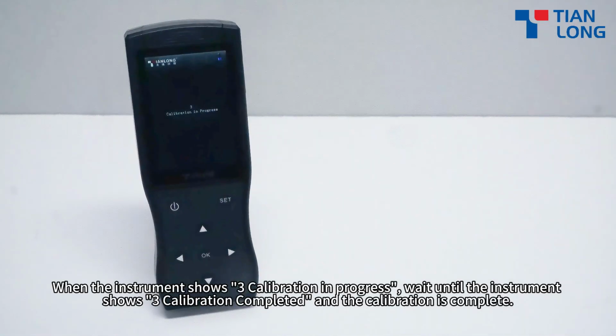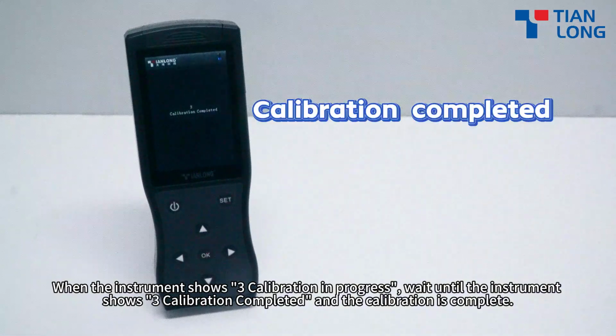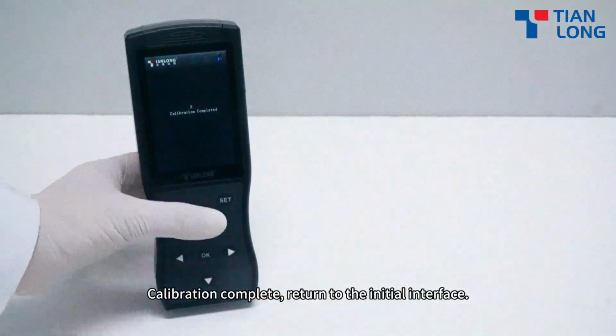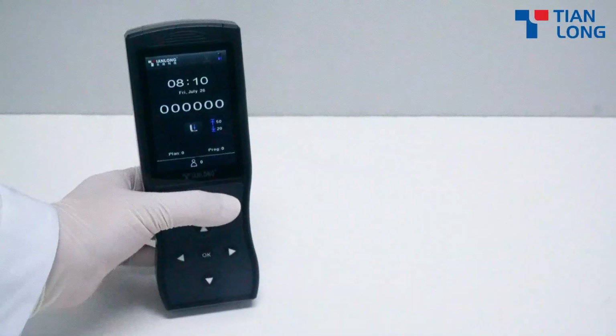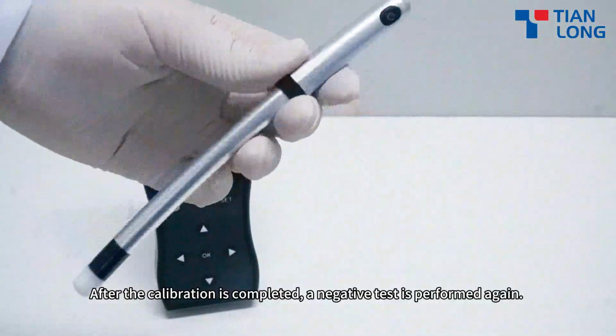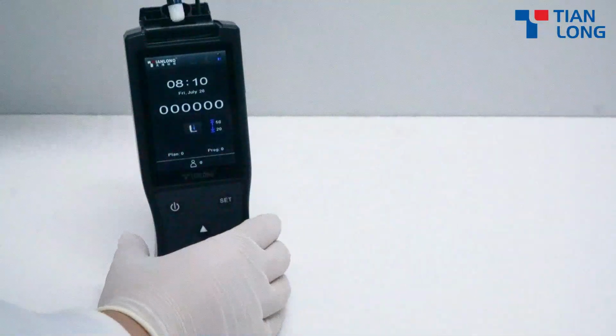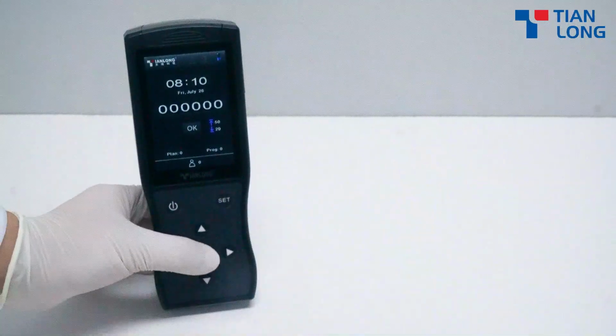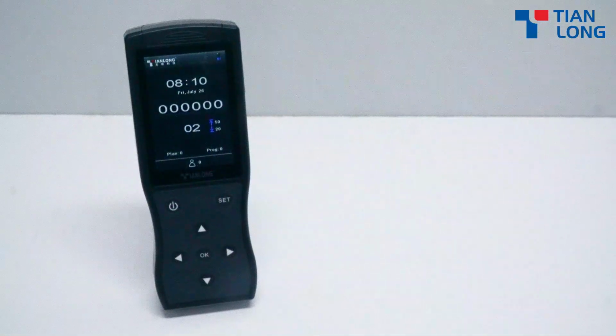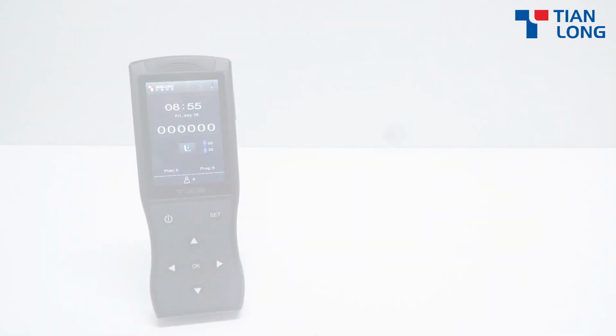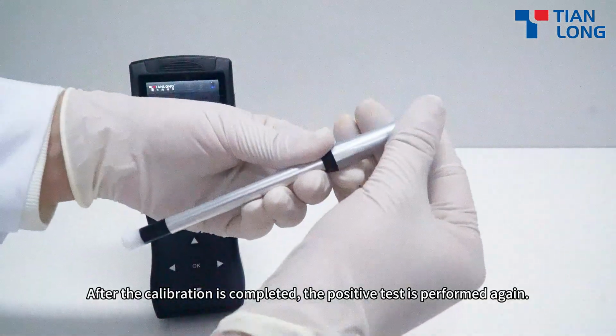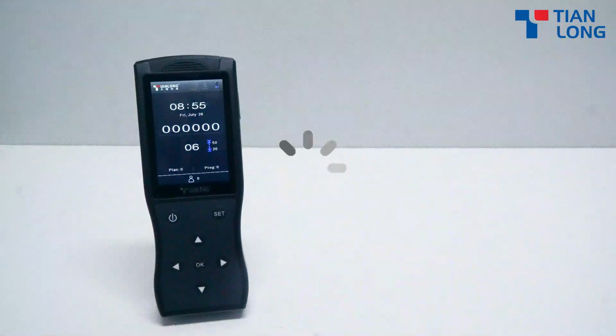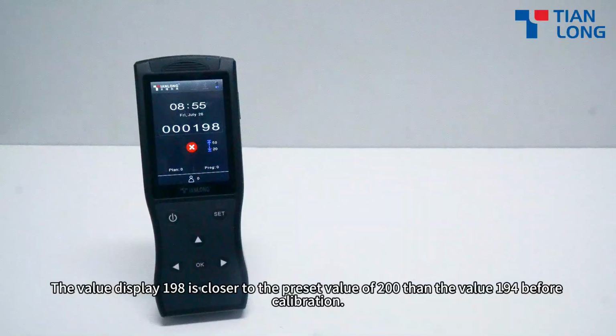When the instrument shows 3 calibration in progress, wait until the instrument shows 3 calibration completed and the calibration is complete. Calibration complete. Return to the initial interface. After the calibration is completed, a negative test is performed again. After the calibration is completed, the positive test is performed again. The value display 198 is closer to the preset value of 200 than the value 194 before calibration.